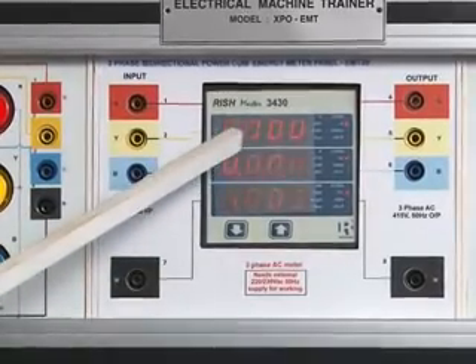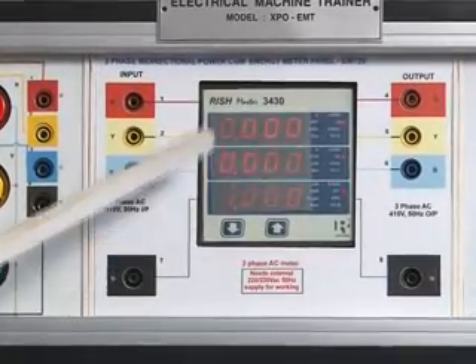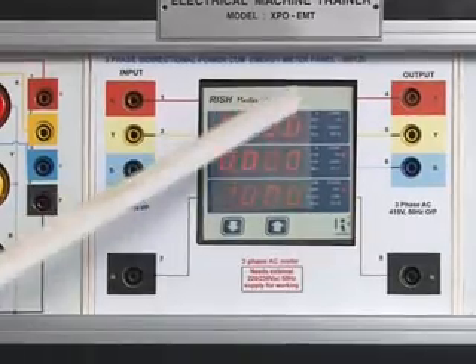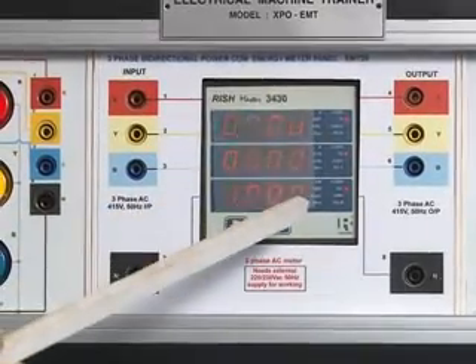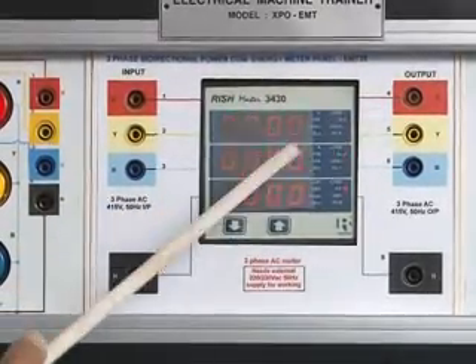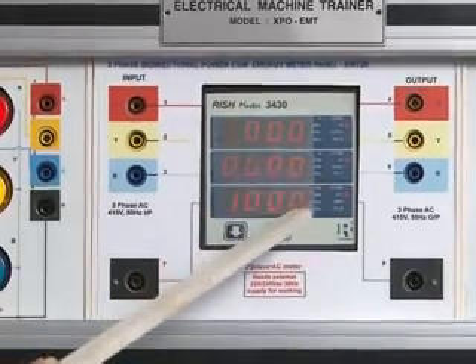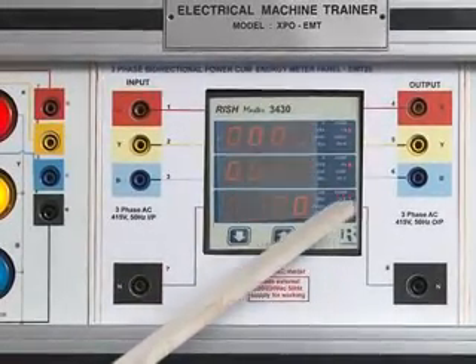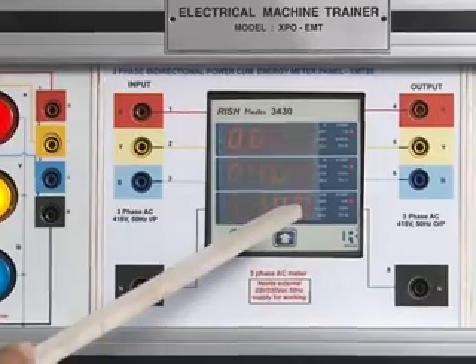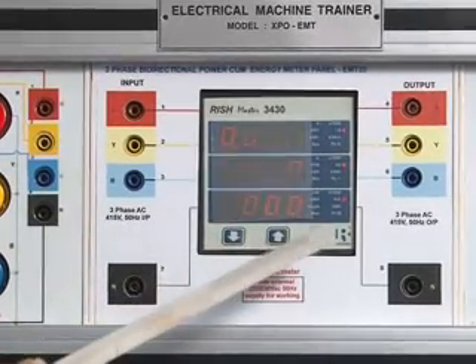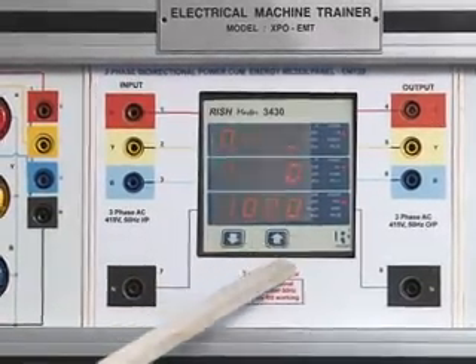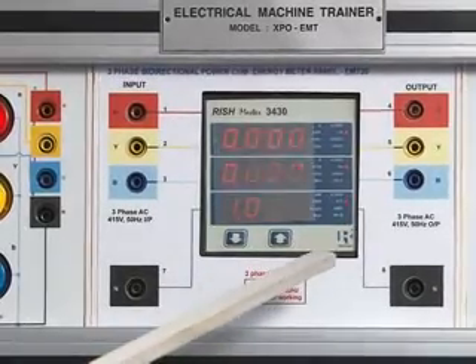This panel is useful to measure the 3-phase R, Y, B various parameters: voltage, current, kVAR, kW, frequency, and other parameters, power factor and wattage.